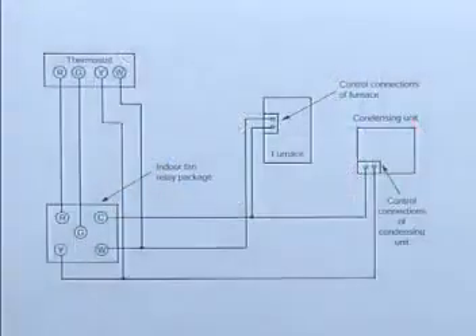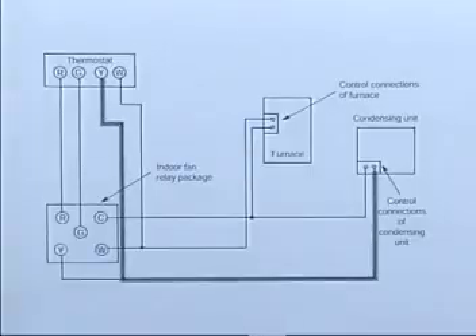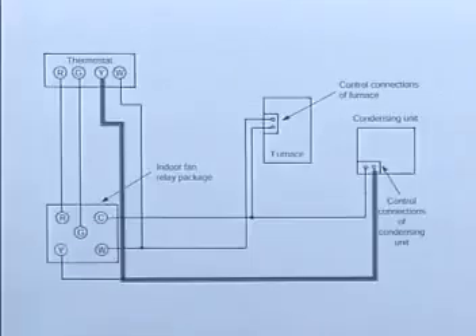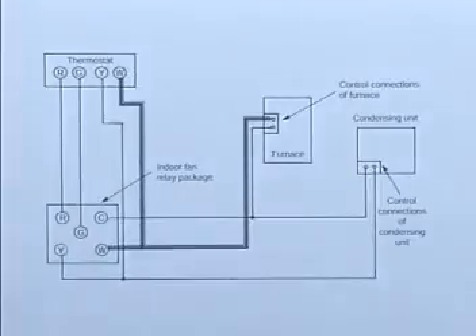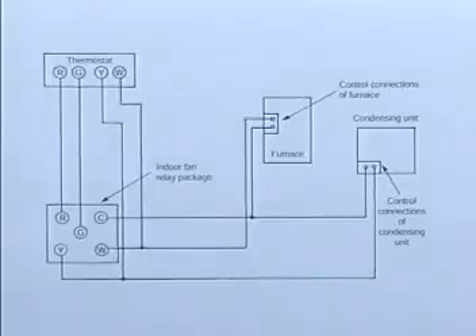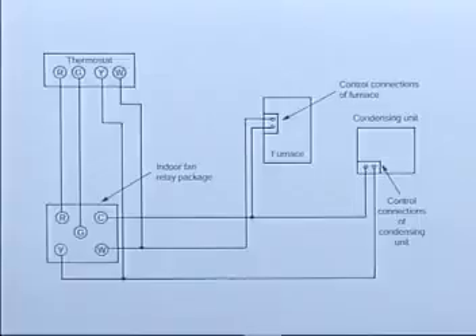Most of the low voltage connections between the condensing unit, thermostat, and indoor unit are made at the fan relay package. You can see from this diagram that the condensing unit is powered by the Y terminal on the thermostat, which provides power when cooling is called for. The heating cycle is controlled by the W terminal on the thermostat, which energizes the furnace when there's a call for heat. The G terminal on the thermostat controls the indoor fan, which is not shown in this diagram since the control wiring for this component is factory installed.